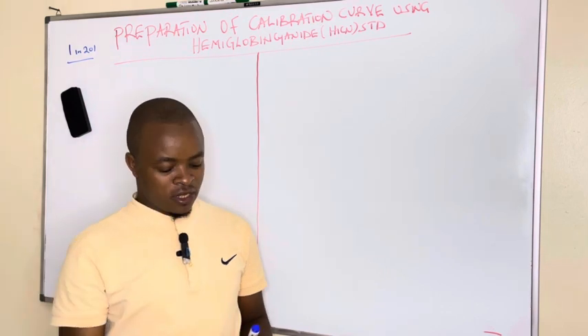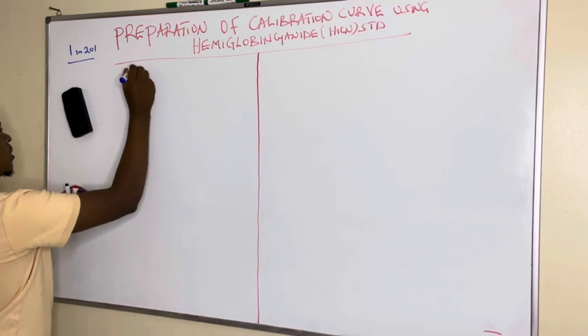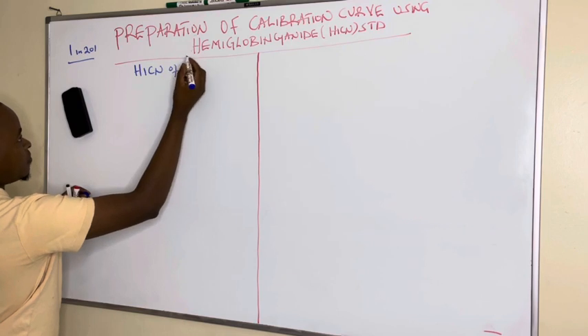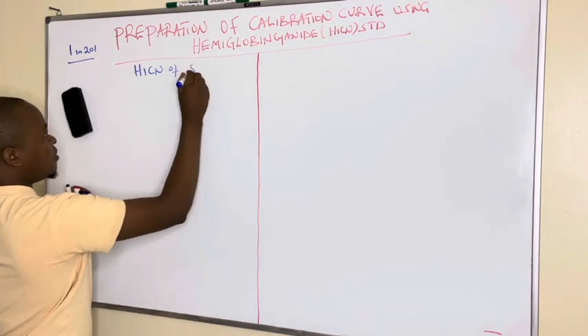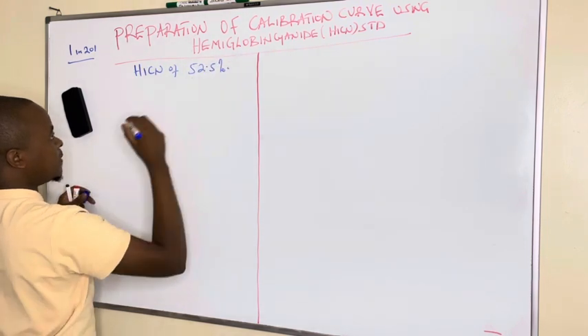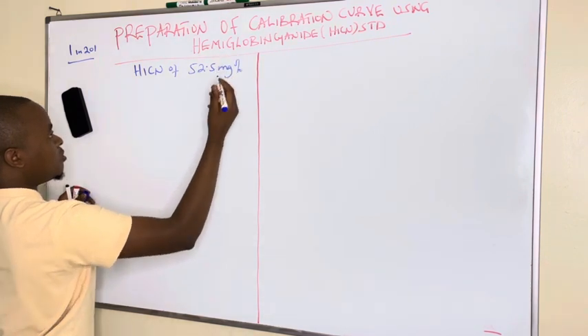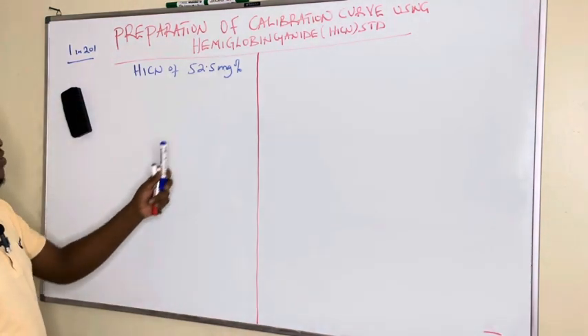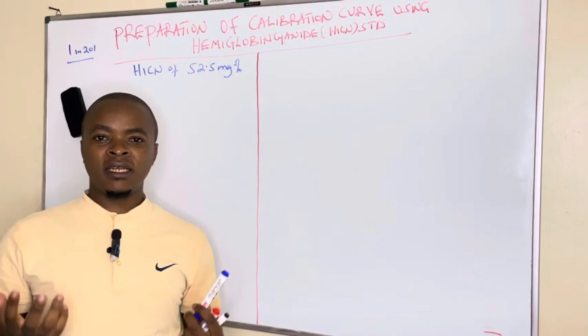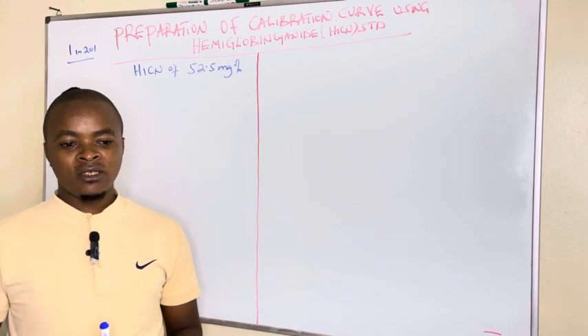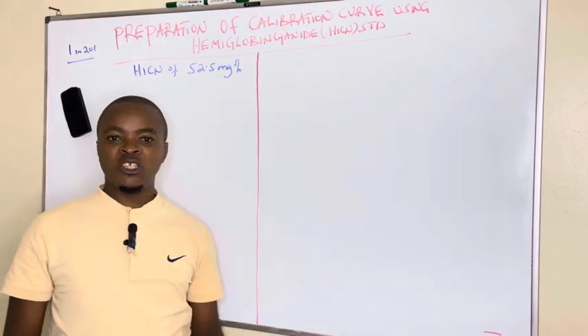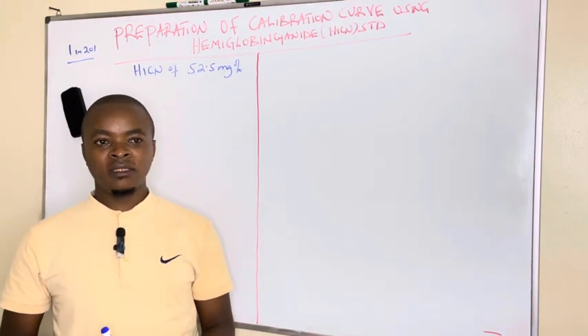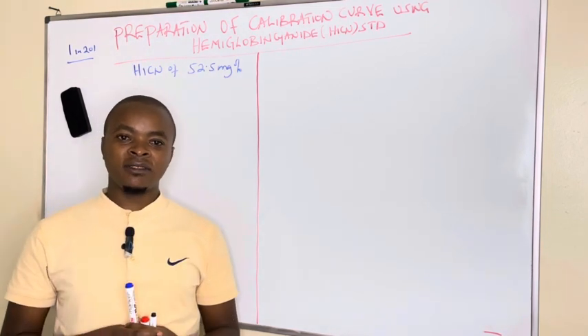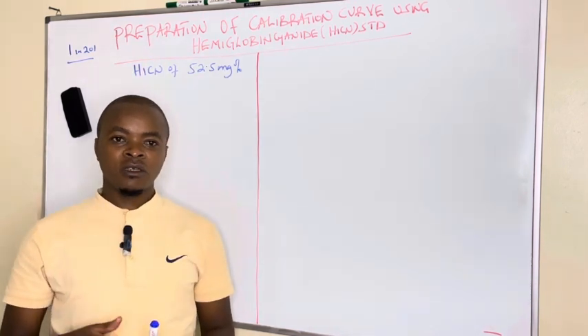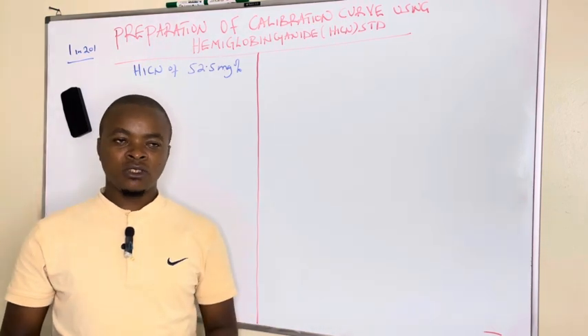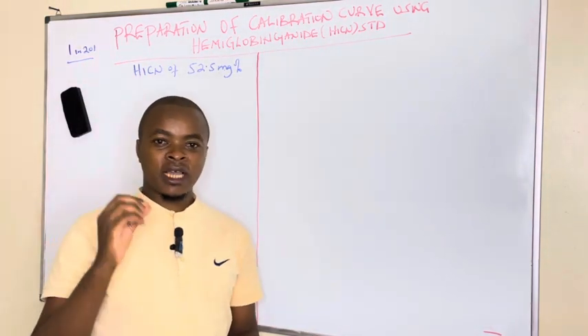But we want to use a single standard. For example, in our discussion today, we are going to use an HiCN, or hemoglobin cyanide, standard of 52.5%, what we normally call milligram percent or milligrams per deciliter. Because cyanide hemoglobin is stable, these ready to use standards are already on the market and can be stored for even 2 years. Whenever you are in the laboratory and want to prepare a calibration curve to determine HB by the Drabkin's method, or cyanide hemoglobin method, they are available. We can always use them to calibrate our colorimeters so that we can develop the curve of HB concentrations versus the absorbances. So we want to use 52.5 milligrams percent as our ready to use standard.